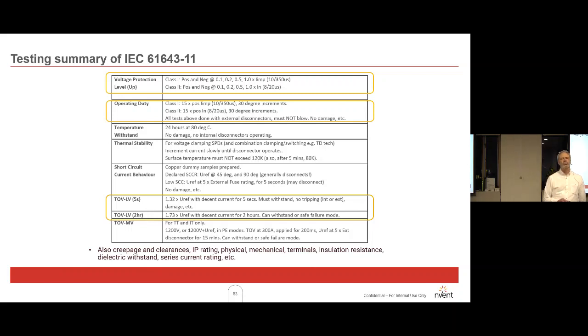This slide relates to classes. The top slide shows you two lines, class 1. Now, surge diverters are tested using an industry standard waveform. There's two standard waveforms commonly used. That's the 10 by 350 microsecond, where it has a 10 microsecond rise time and a 350 microsecond decay time, and the 8 by 20, which has been commonly used in New Zealand and Australian standards for many years. And the European standards have recognised class 1, and possibly that will be more recognised by our new standard. Don't quote me on that though.